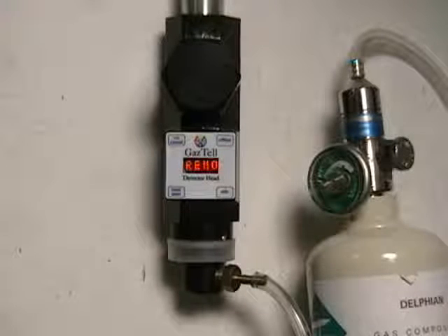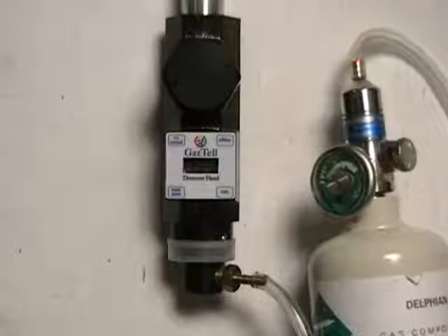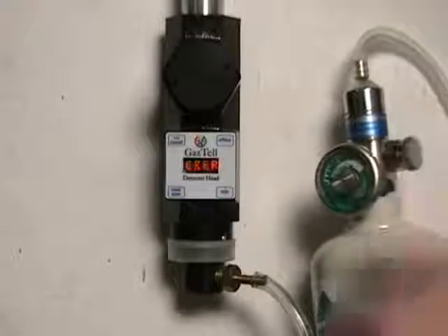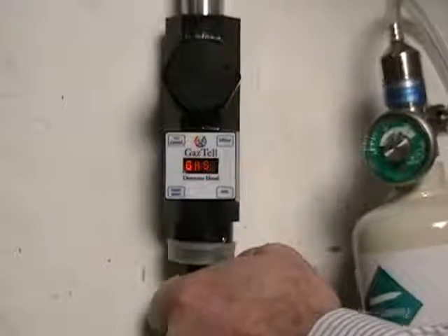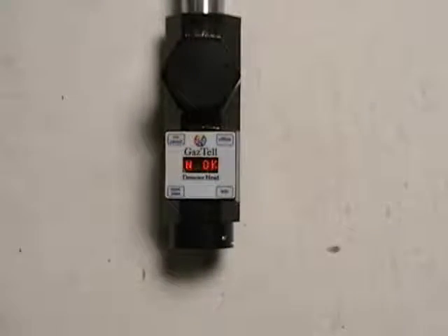After a successful span calibration, Span OK, Remove Span Gas will be displayed. Turn off the regulator valve and remove the calibration cup. The gas will slowly dissipate from the sensor chamber, but this can be sped up by applying zero air to purge the gas. The detector head will display the gas reading, but will not resume normal operation until the gas has dissipated to less than 5%.